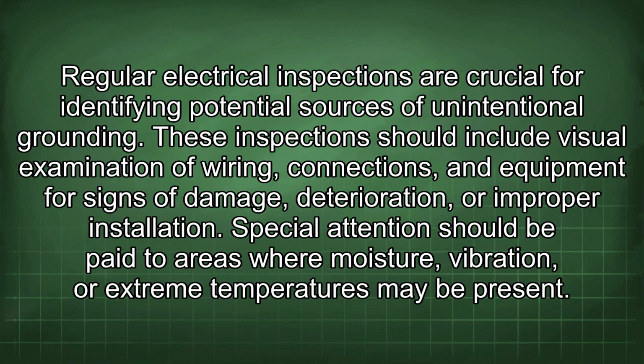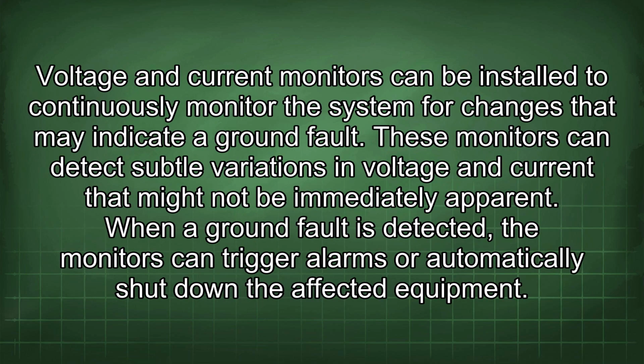Regular electrical inspections are crucial for identifying potential sources of unintentional grounding. These inspections should include visual examination of wiring, connections, and equipment for signs of damage, deterioration, or improper installation. Special attention should be paid to areas where moisture, vibration, or extreme temperatures may be present. Voltage and current monitors can be installed to continuously monitor the system for changes that may indicate a ground fault. These monitors can detect subtle variations in voltage and current that might not be immediately apparent. When a ground fault is detected, the monitors can trigger alarms or automatically shut down the affected equipment.